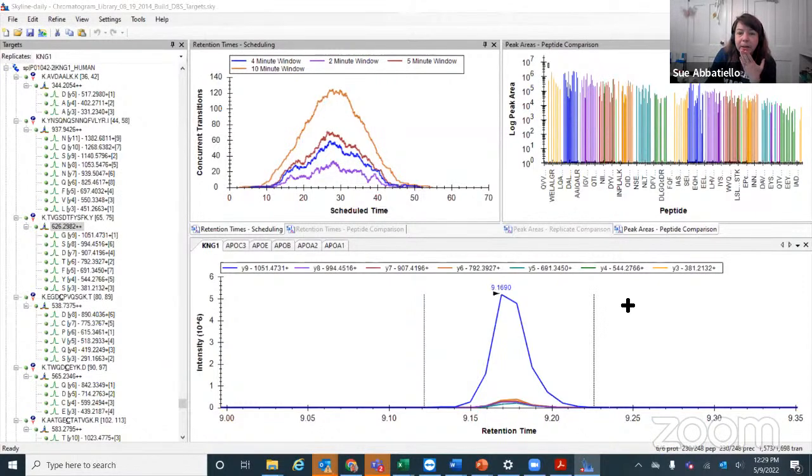See, if doing targeted MRM assays on a UPLC triple quad, what adaptation to the instrument yields the most significant increase in sensitivity? Yeah, you can do microflow on modern UHPLCs for sure, or even higher flow. And it really just depends on if you can detect the thing that you're looking for. And the important things here are chromatographic resolution, narrowing the peak. So columns that use super small beads will always have a good resolution effect, like less than 2 micron particle beads versus columns that use 3 micron. Their peaks will be broader under the same chromatographic conditions.